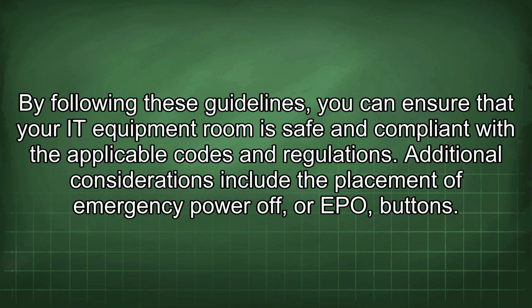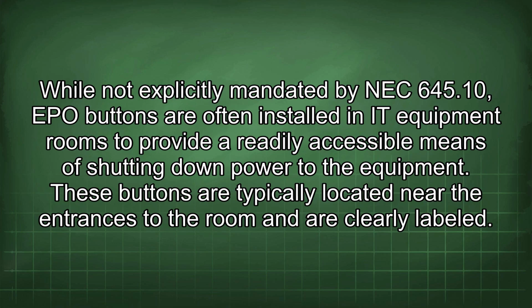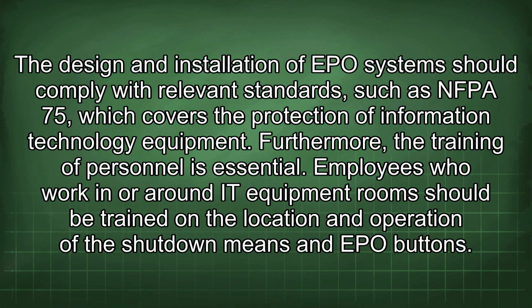By following these guidelines, you can ensure that your IT equipment room is safe and compliant with the applicable codes and regulations. Additional considerations include the placement of emergency power off, or EPO, buttons. While not explicitly mandated by NEC 645.10, EPO buttons are often installed in IT equipment rooms to provide a readily accessible means of shutting down power to the equipment. These buttons are typically located near the entrances to the room and are clearly labeled.